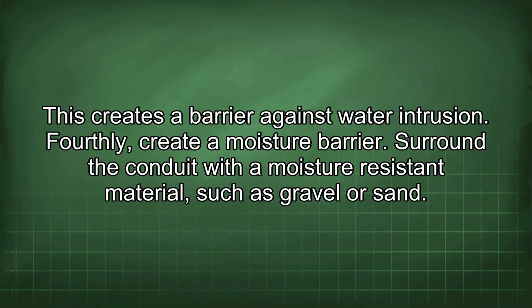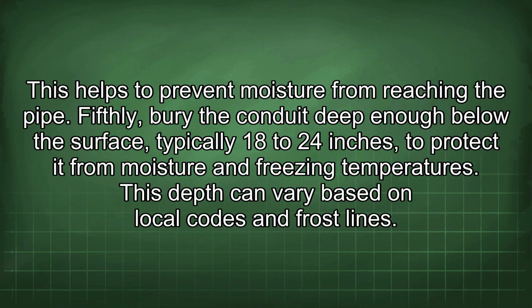Fourthly, create a moisture barrier. Surround the conduit with a moisture-resistant material such as gravel or sand. This helps to prevent moisture from reaching the pipe. Fifthly, bury the conduit deep enough below the surface, typically 18 to 24 inches, to protect it from moisture and freezing temperatures. This depth can vary based on local codes and frost lines.